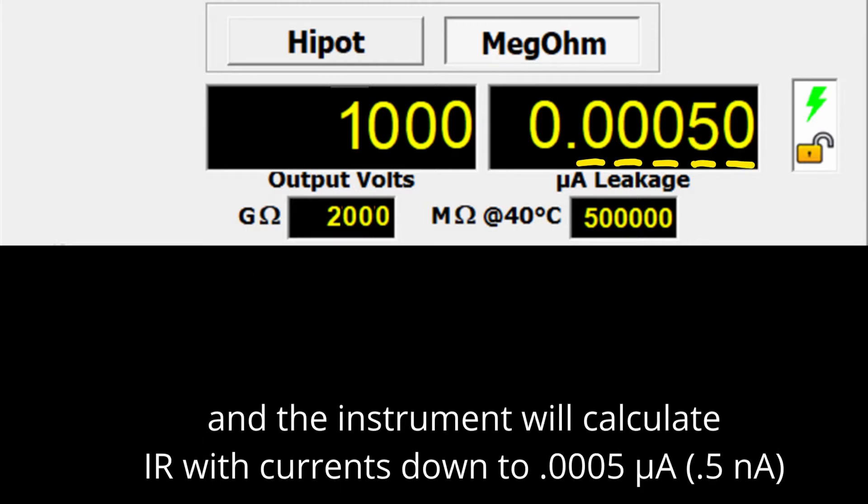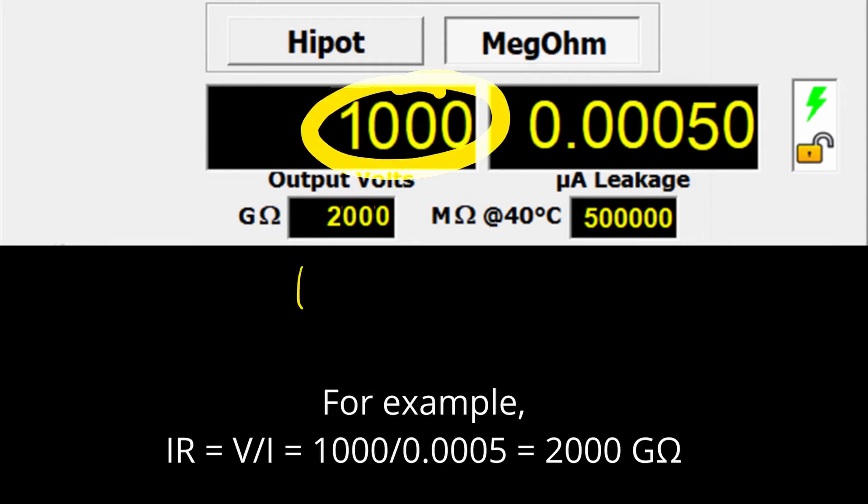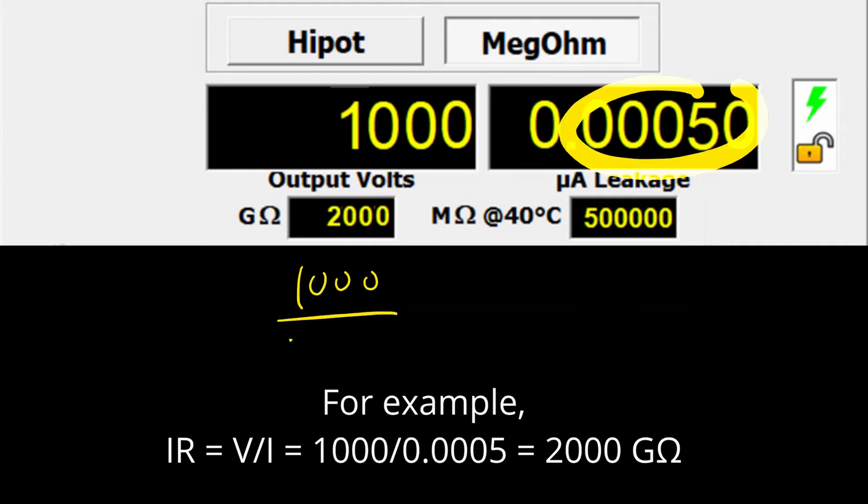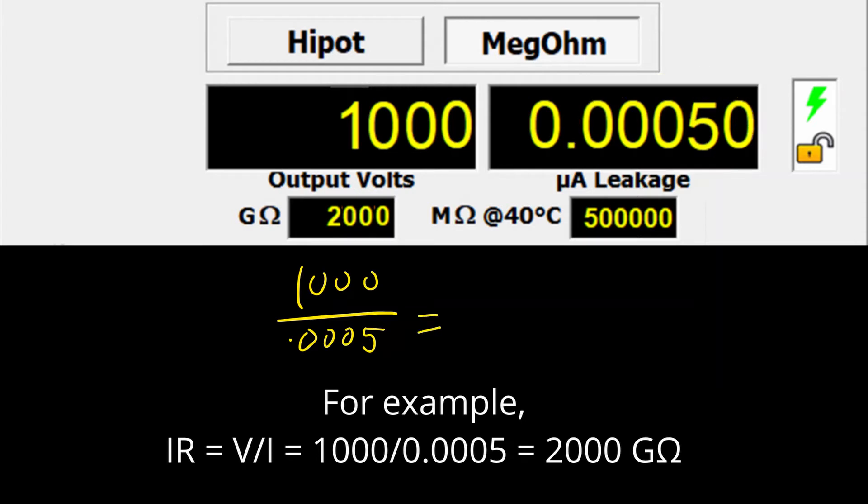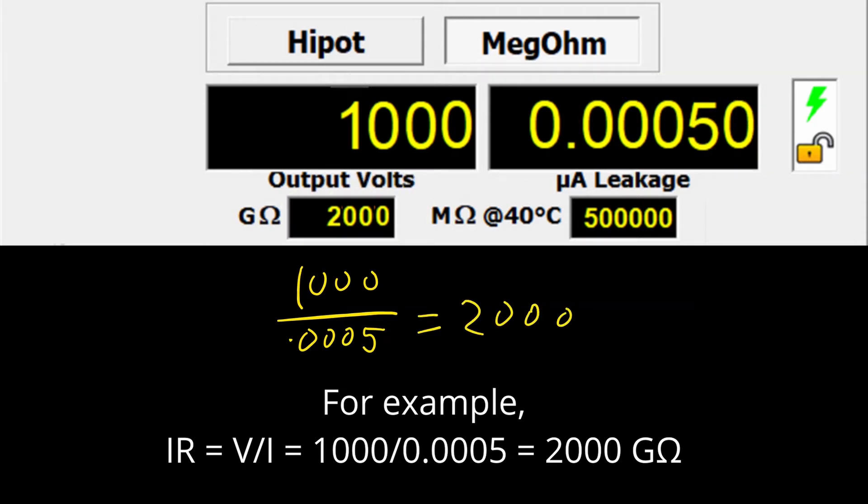The instrument will calculate megaohms with currents down to 0.0005 microamps or 0.5 nanoamps. Ohm's law states IR equals voltage divided by current. For example, if the test voltage is 1000 volts, IR can be calculated up to 2000 gigaohms.